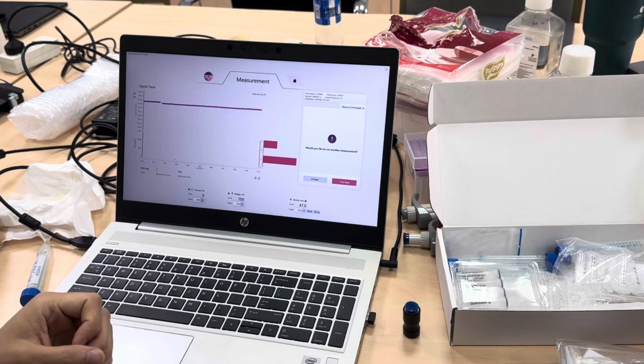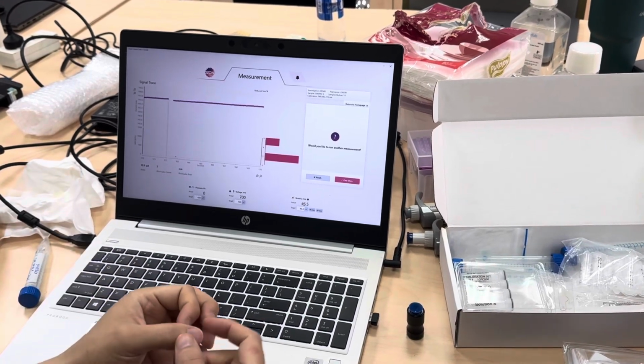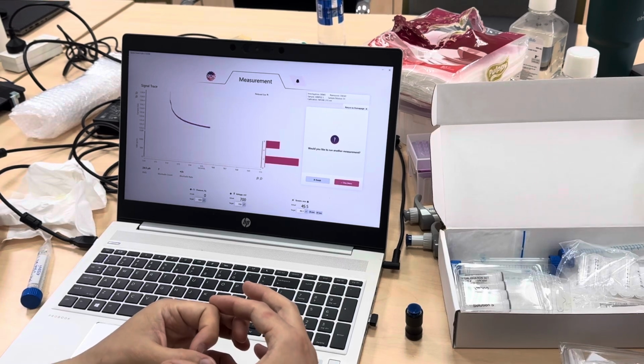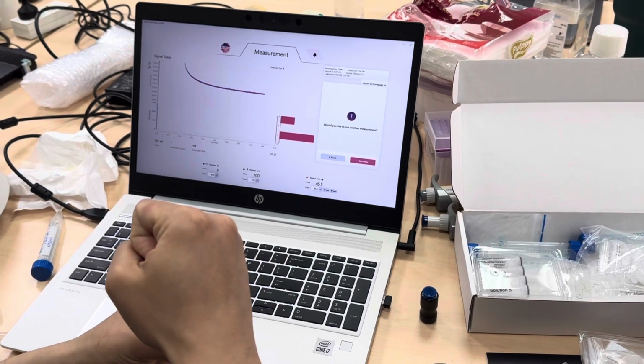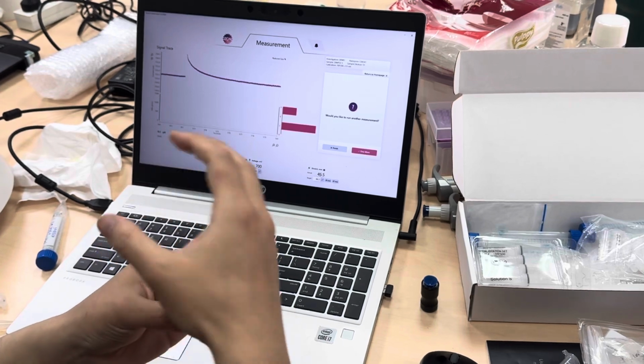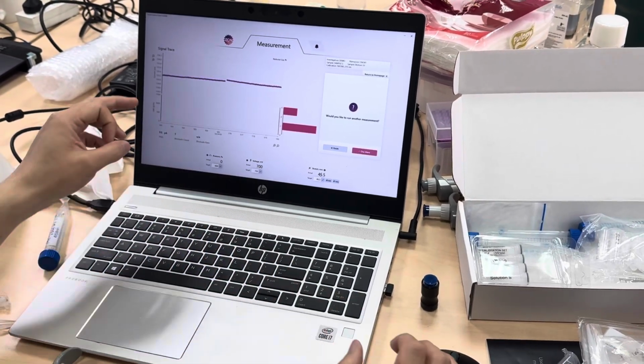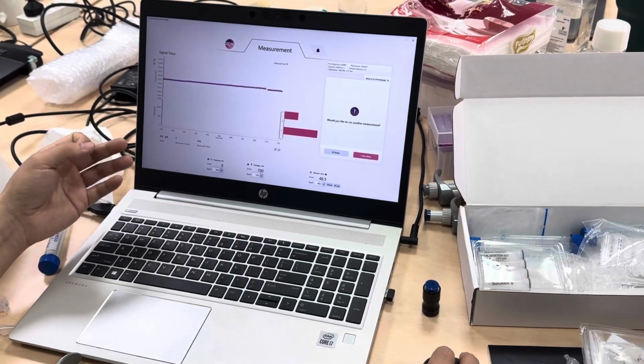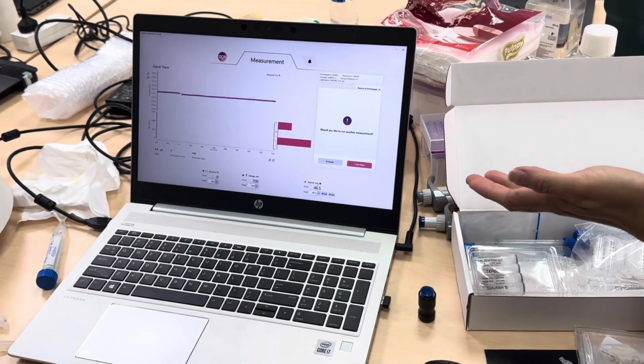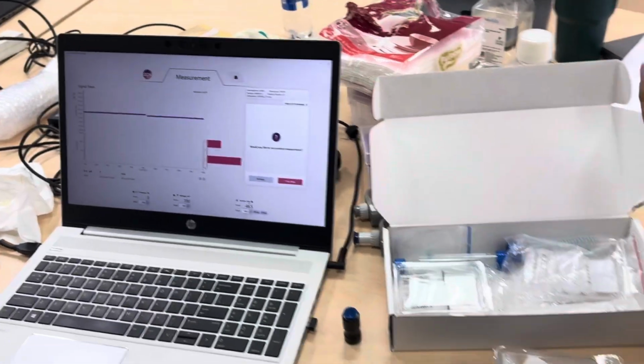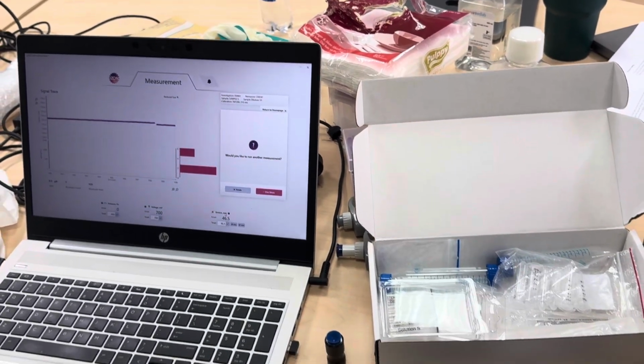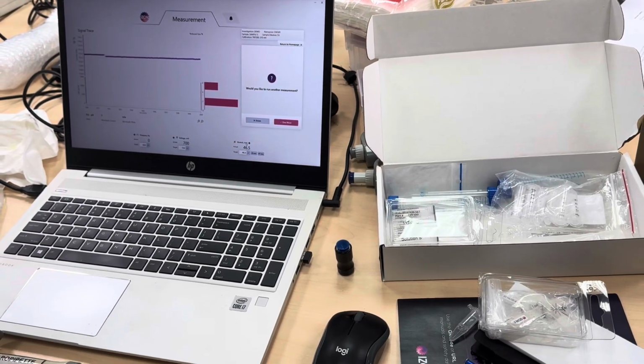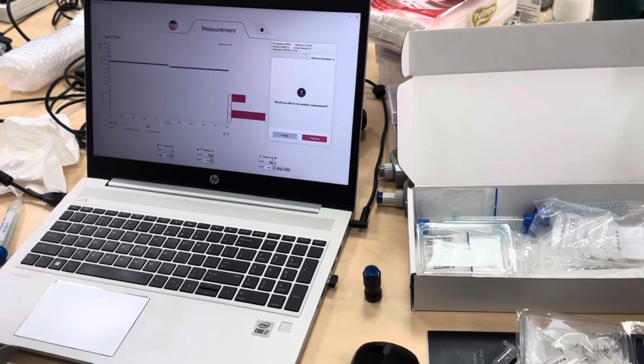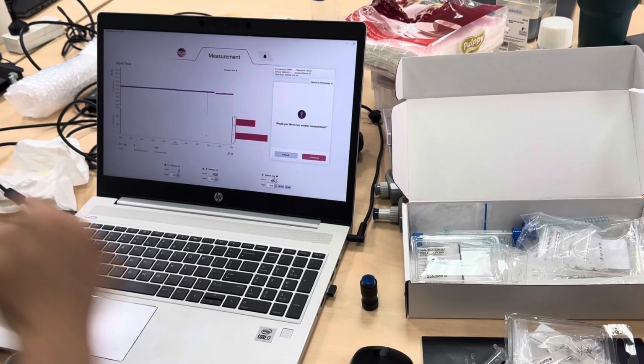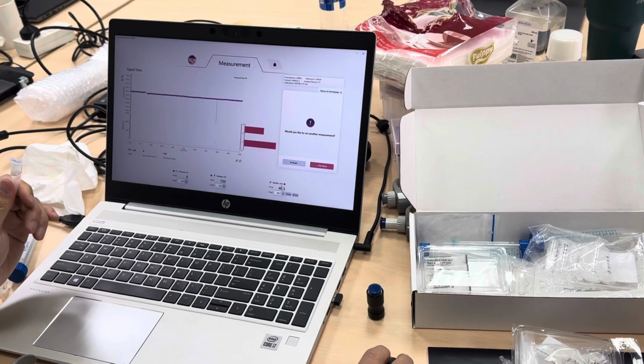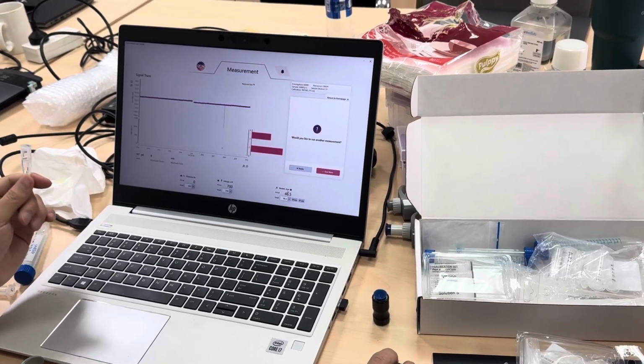Because we reduce the structure, the hole size gets smaller, and then for the same particles the blockage will be larger, returning to 0.2. That's the place where we need to do another calibration, but this one is only a calibration in the software. Every time we still need to use the actual calibration particles, because it records a new set of data under these conditions. So after 3 or 4 samples, we recalibrate and continue.